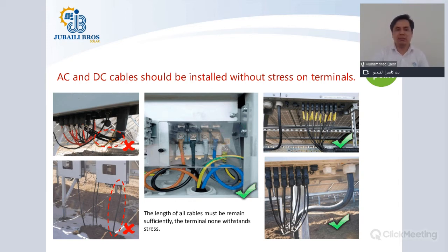AC and DC cables should be installed without stress on the terminal. As you know, with Huawei inverters, you do not need a DC combiner, because Huawei inverters are made with a fuseless design. When you are bringing your string connection from the solar panels, you can directly terminate it to the solar inverter. Sometimes we have seen that the EPCs, the contractors, the subcontractors are not following the guidelines of the user manual, which strictly mentions that you should not be putting stress on the terminals of the inverter.